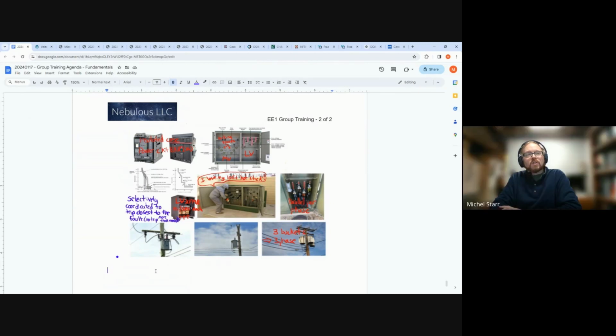No, you would see this. I'd say the most common place would be a medium voltage or unit substation lineup. But they're excellent. The use of IR windows, as I noted before about NFPA 70B for maintenance of electrical systems, is becoming a standard. These kinds of accessories are being added at the original equipment manufacturer level.